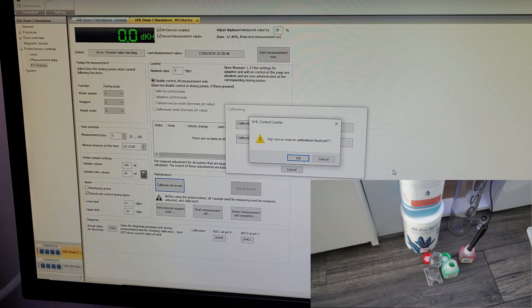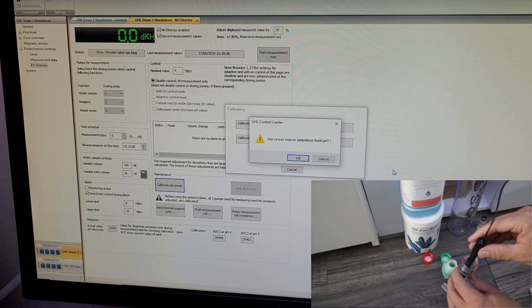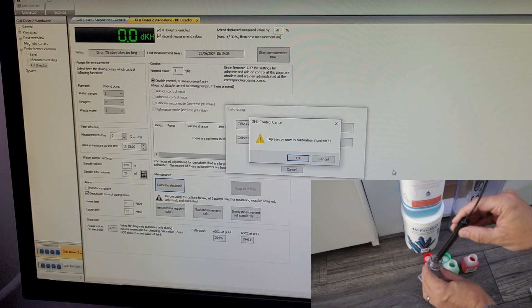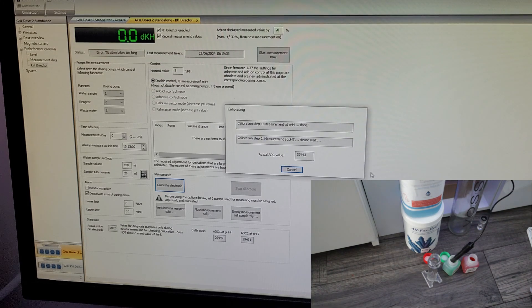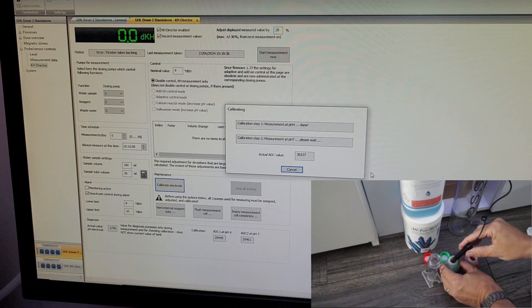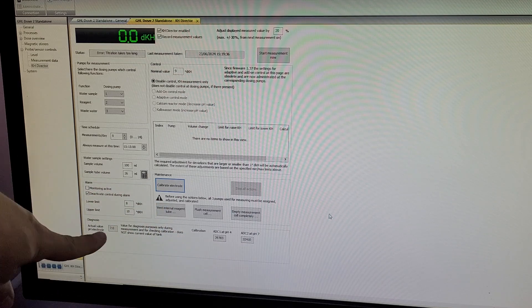That's done - it wants us to dip it into pH 7 fluid. I'm going to take it out of the 4, just dip it into the RO water, bring it out, shake it off a little bit, and then pop it into the 7. Press OK and we'll see what this one does. That's finished - we save the calibration, yes please. The values have now changed: we've got 39,783 and 32,410. And look at that - the pH reading is bang on 7. So let's give it a go!